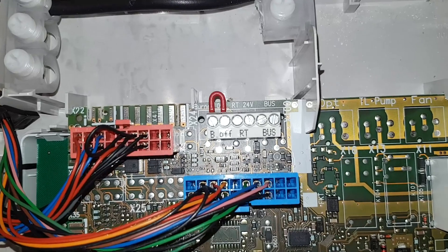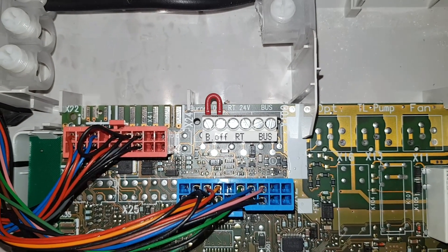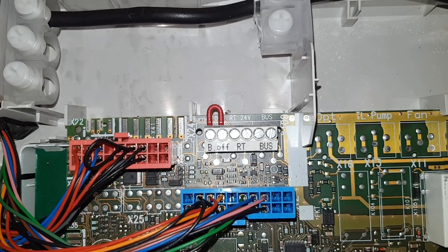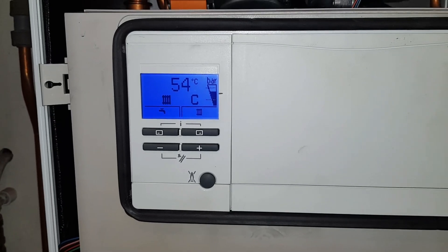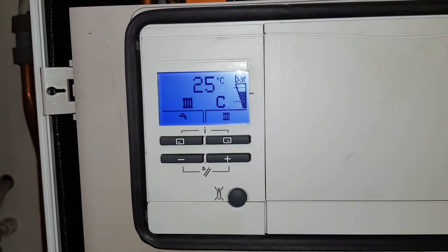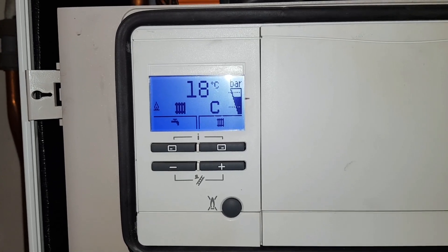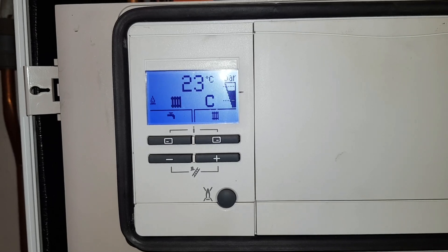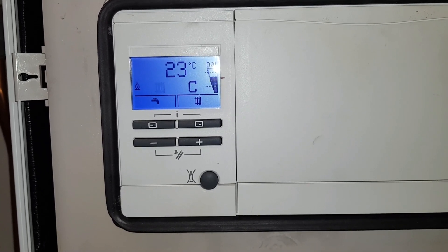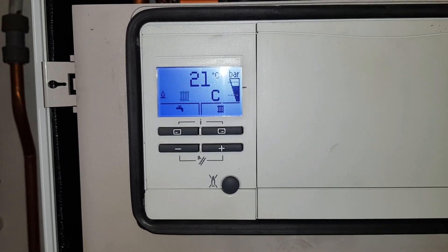Now we're looking at the PCB and you can see where it's set to 24 volts — there's no link there. With no link there and no external controls, we're not going to get any demand. So we're going to put a link in there and see if the boiler starts for heating. We've put the link in — now look at the display. You can now see the radiator symbol, which means we now have a demand for heating. The burners are firing up, you can see the burner light come on. So there was no link on the 24 volt supply, and that's why we had no heating. And also it was turned off with that umbrella symbol as well.